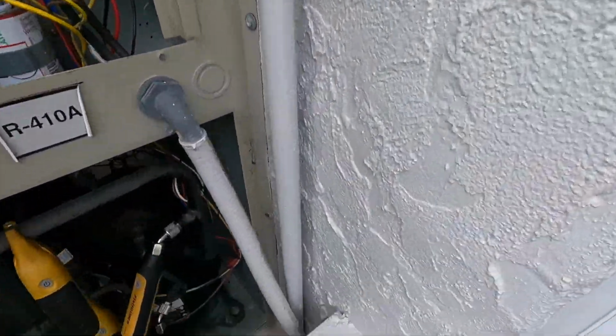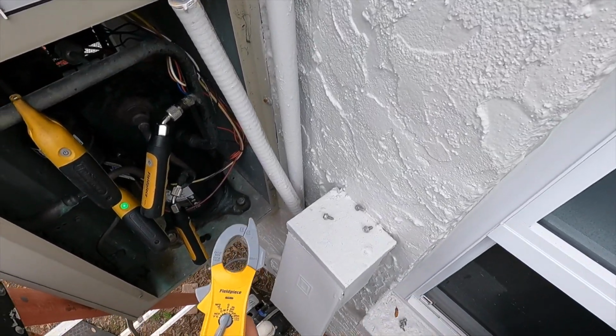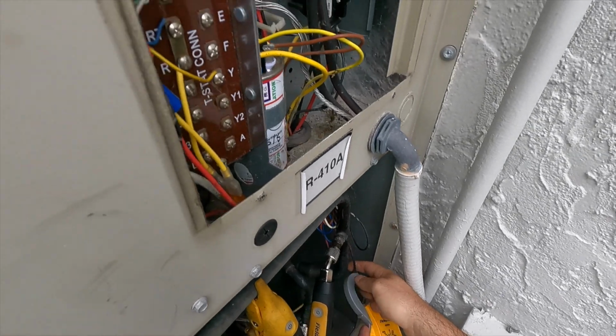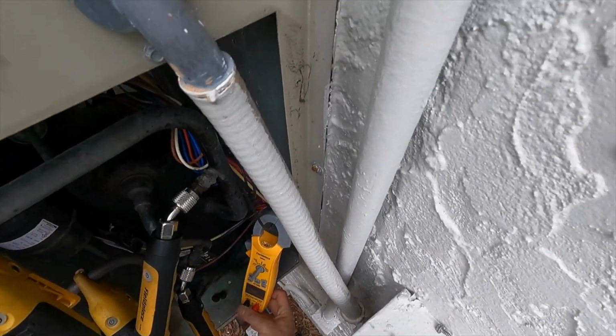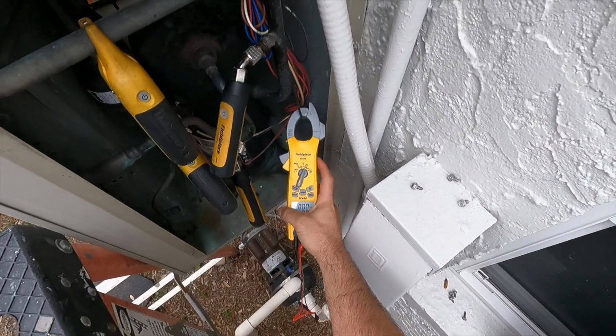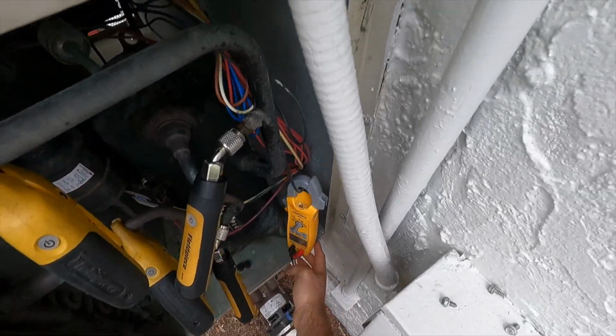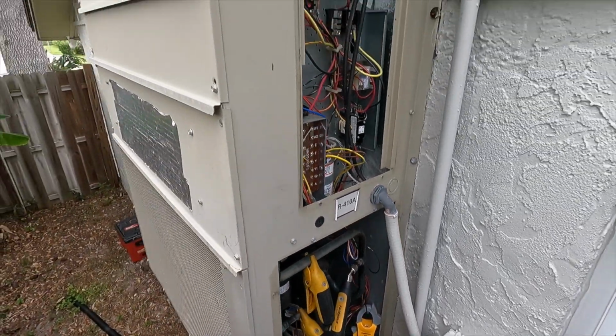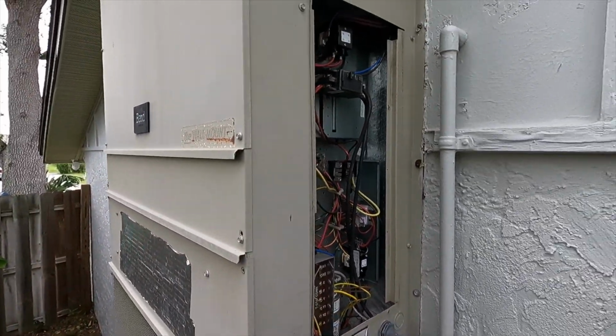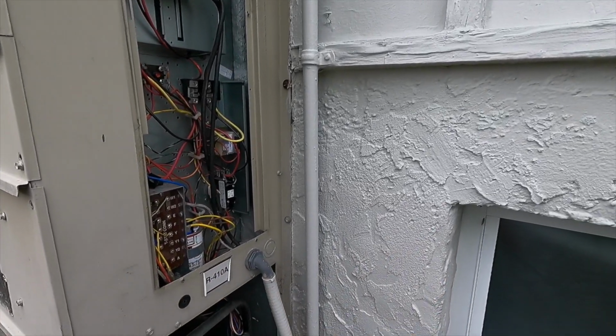For now, we're going to go ahead and take the lock rotor amp draw. All right, so now that we got the system off, we're going to go ahead and take a lock rotor amp draw. So we want to know what the inrush amp is for this compressor on start. I'm going to give it a minute here to cool off for a second before we fire it right back up after turning it off.